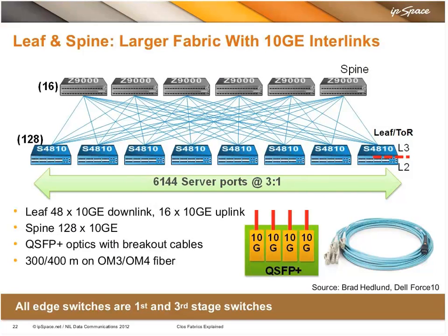As we mentioned on the previous slide, we were using a 3 to 1 oversubscription at the leaf switch, which is also the top of rack. That meant 48 10-gig ports going into the server cabinet, and 160 gig of bandwidth as the uplink going to the spine layer. We were provisioning that 160 gig by using 4 ports of 40 gig as the uplink out of the top of rack.